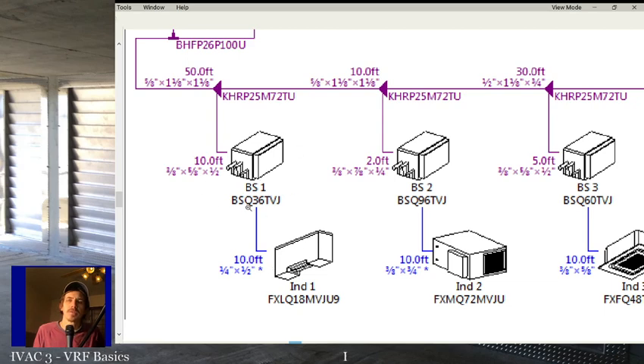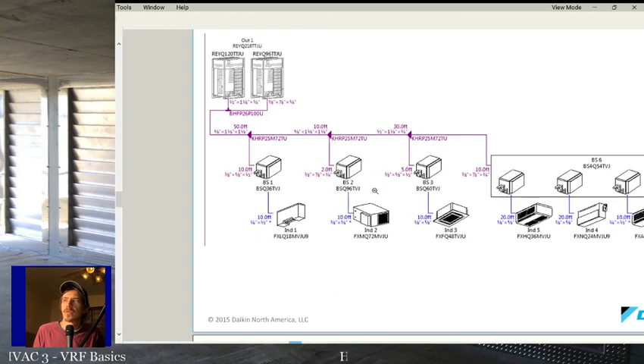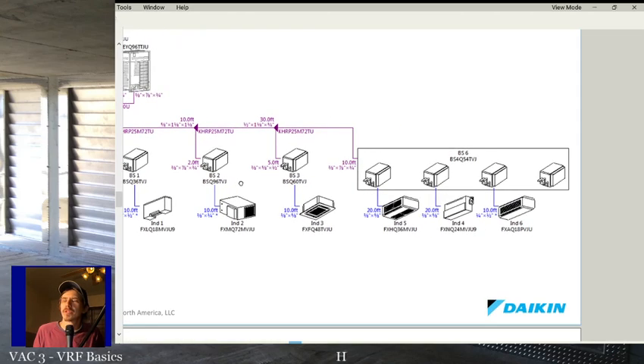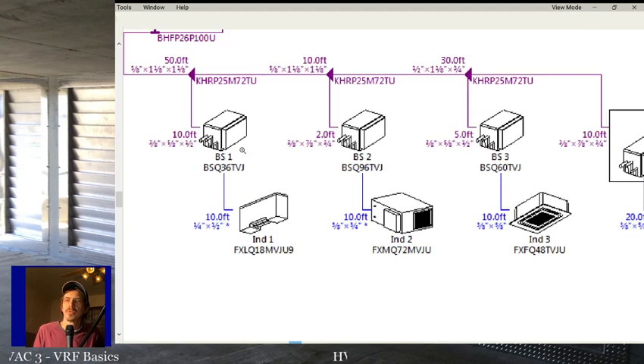And this is what allows you to switch between heating and cooling. Now, they don't actually show one on here, but you can have 2 units connected to a single branch selector. So out of the branch selector, you could T off or Y off and hit another indoor unit, but anything after a branch selector has to be operating in the same mode at all times. So if you have 2 indoor units to 1 branch selector, both of those indoor units need to be in heating, or both of those indoor units need to be in cooling.